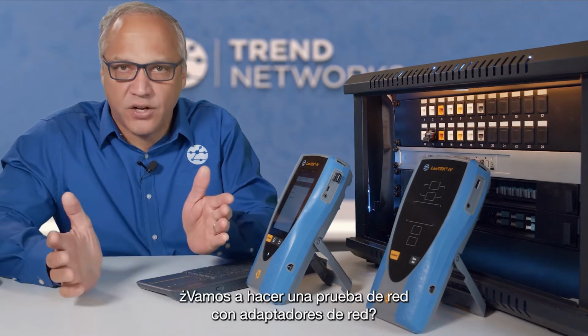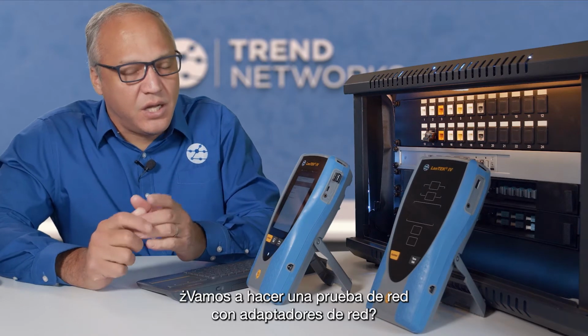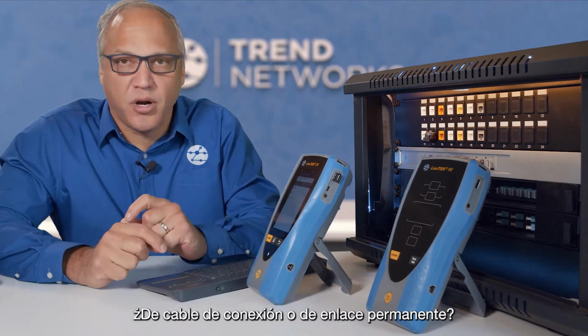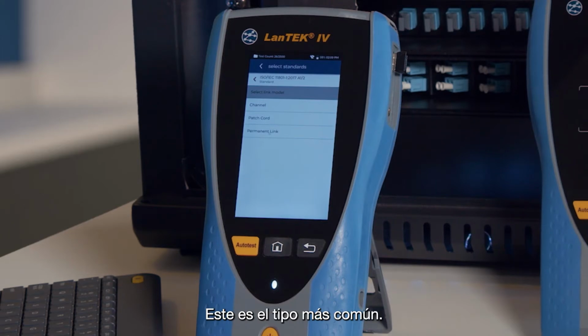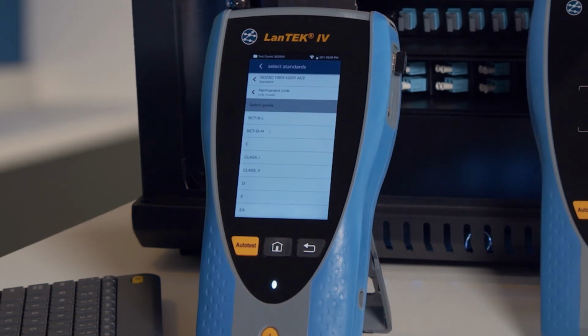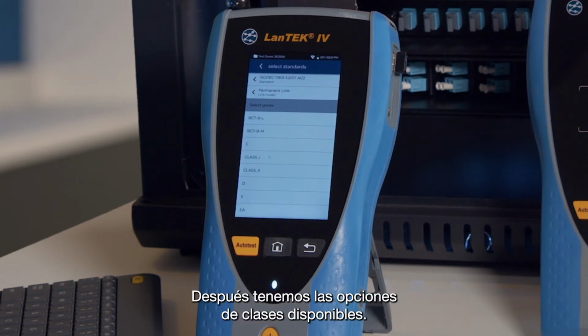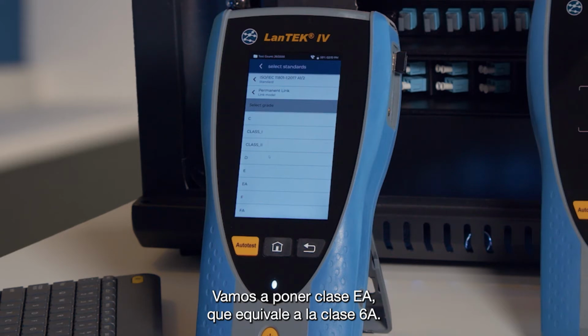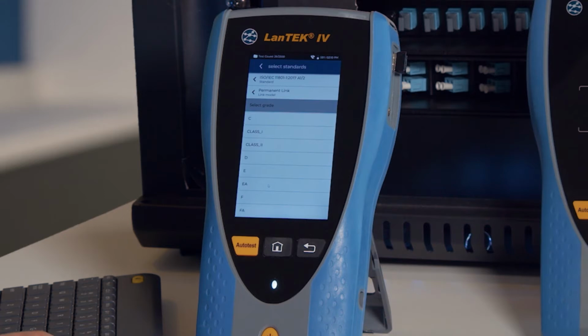So are we doing a channel test with channel adapters, a patch cord test, or a permanent link test? So let's set up permanent link. That's going to be the most common type. And then we have the different classes available. So we'll go down and do a Class EA, which is equivalent to a Class 6A.